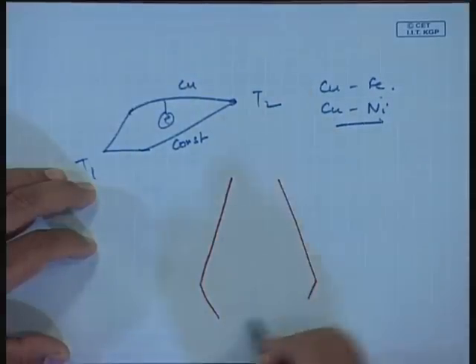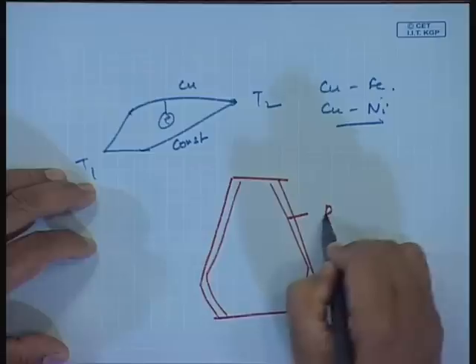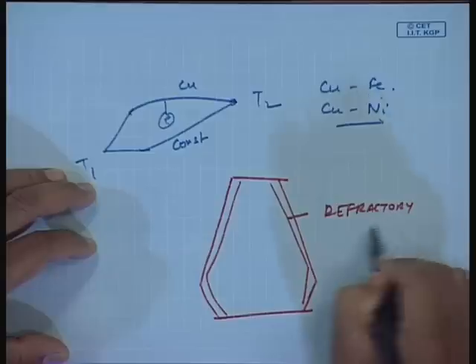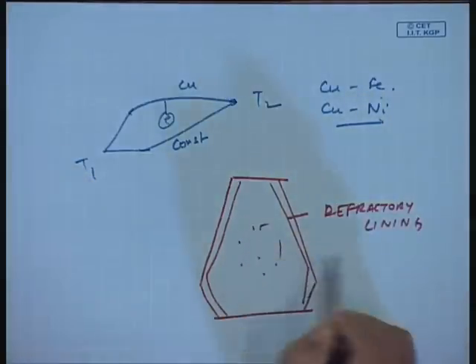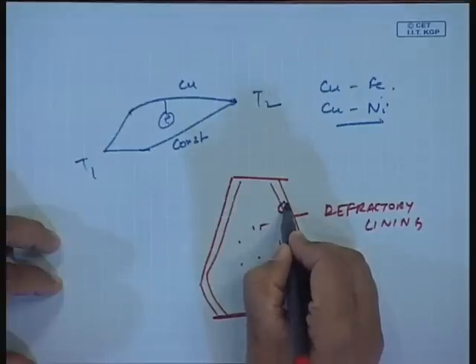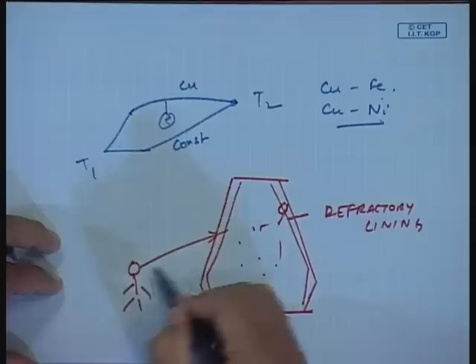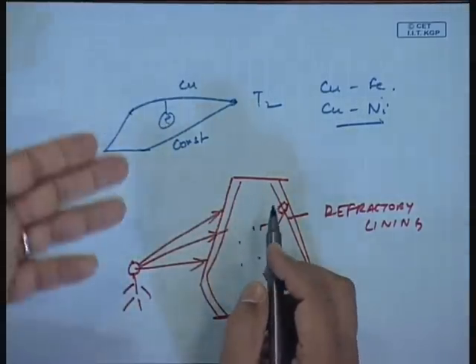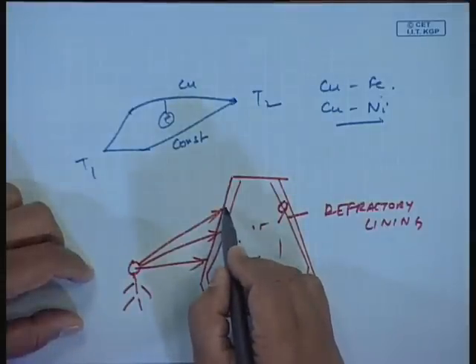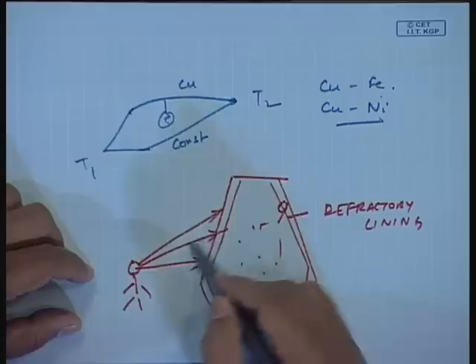In a blast furnace, there is a refractory lining and very high temperature operations inside. What happens when the blast furnace ages? Some of this refractory lining may weaken or break off. If somebody standing next to the blast furnace does a thermal scanning - either through a thermal imaging camera or an infrared temperature detector - they will see some hot spots where the temperature has suddenly increased because the refractory thermal insulation has deteriorated.